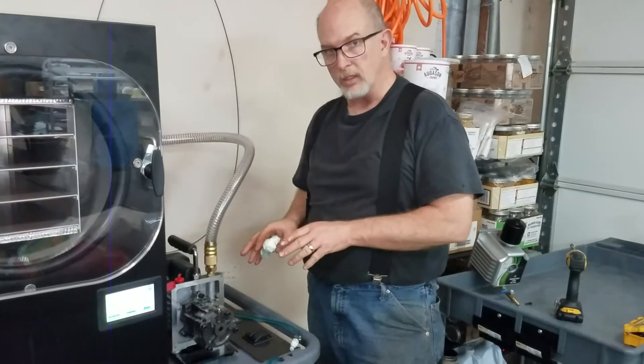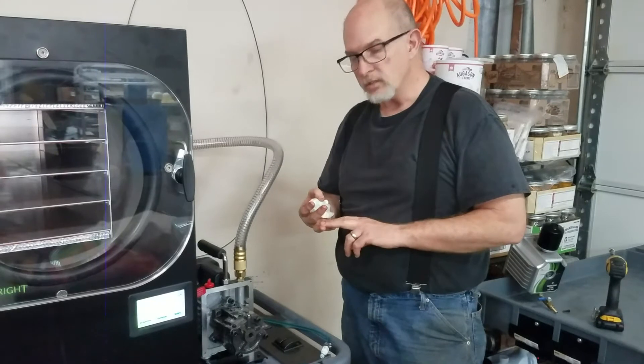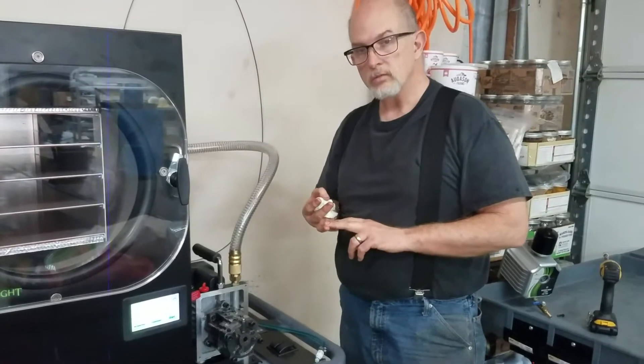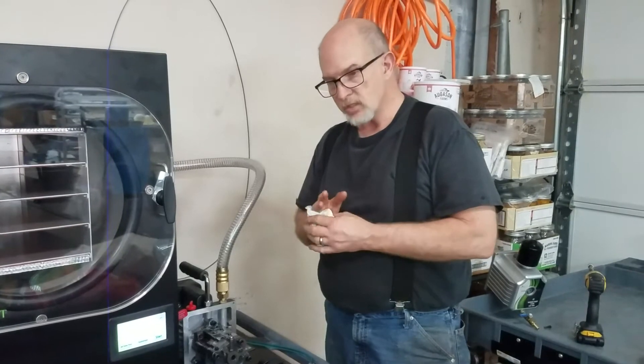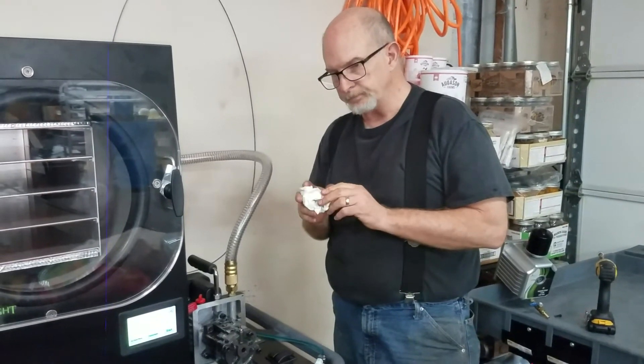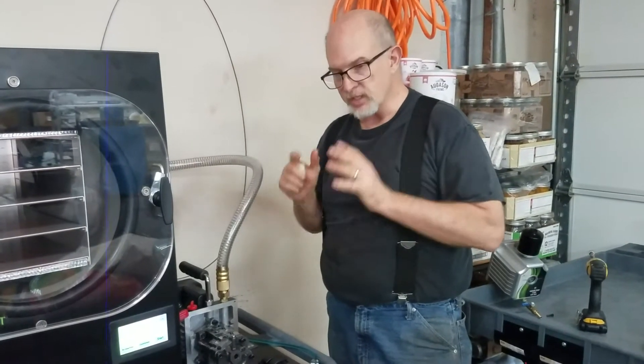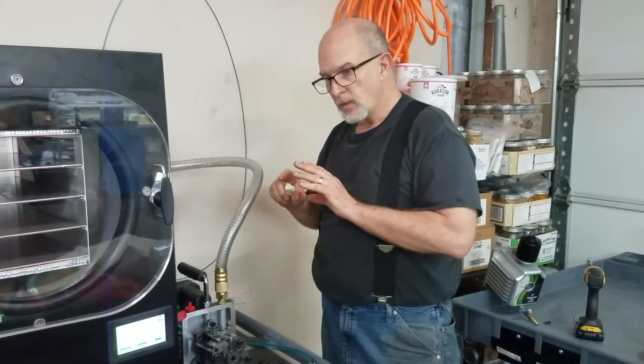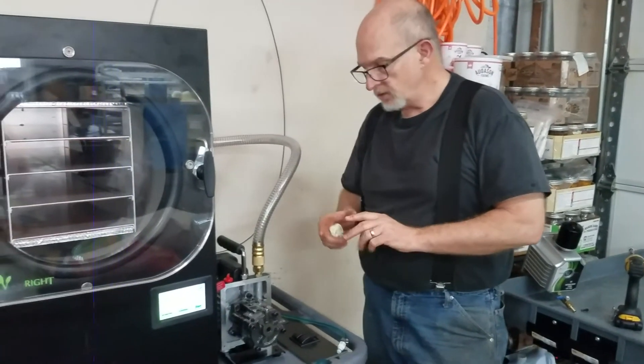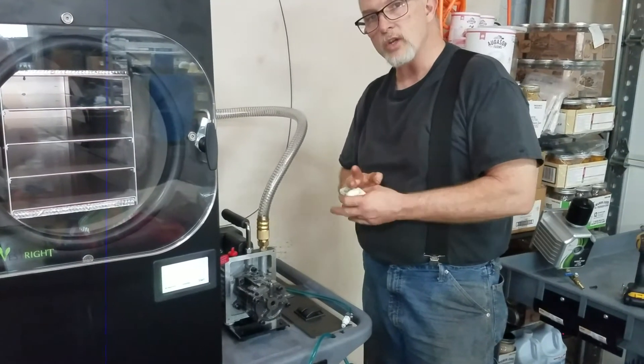This is how a piece of machinery should look when it's used and taken care of properly. In order to take care of this machine in this environment — which is high water and particulates — you need two things. You need the Dairyland oil, or its sister product, which I believe is the same blue oil for the milking industry. And the second thing is to filter your oil — filter it while you're running.